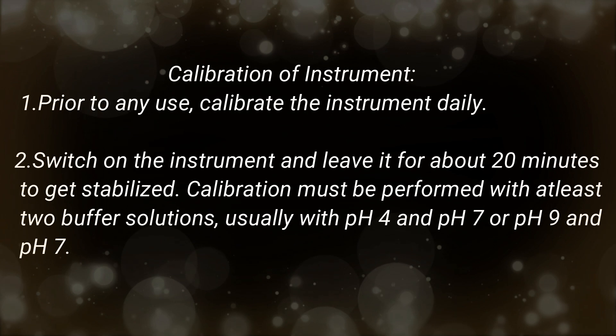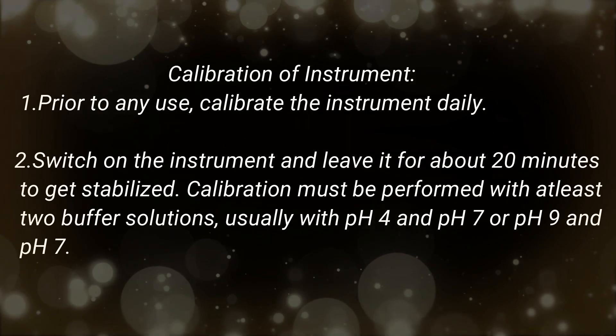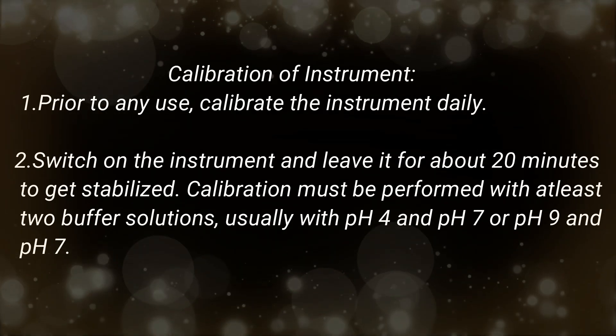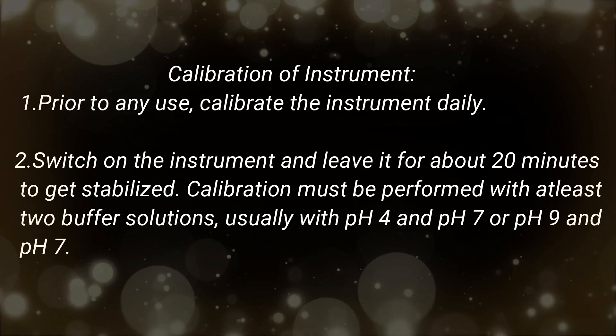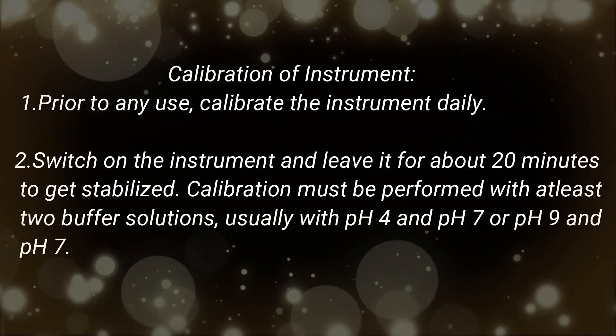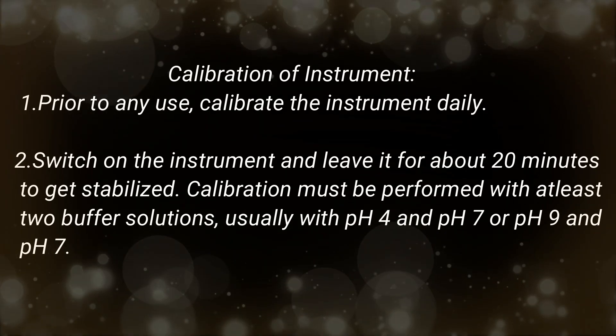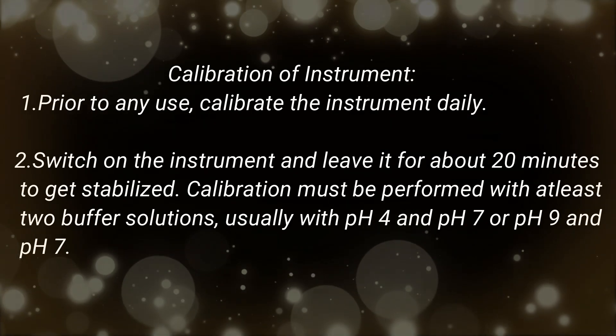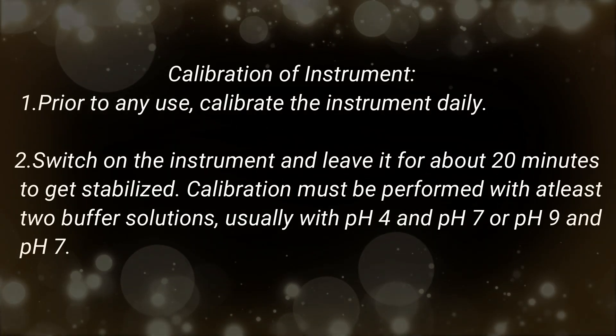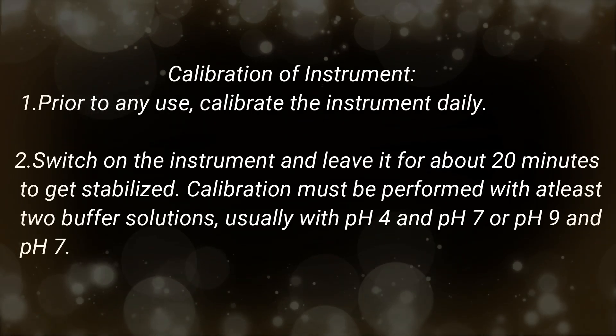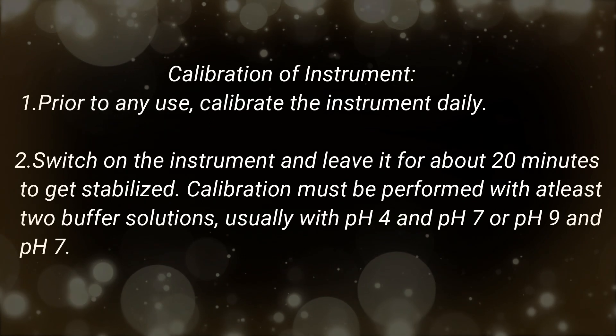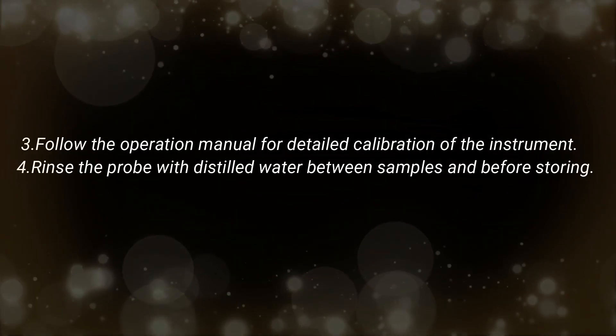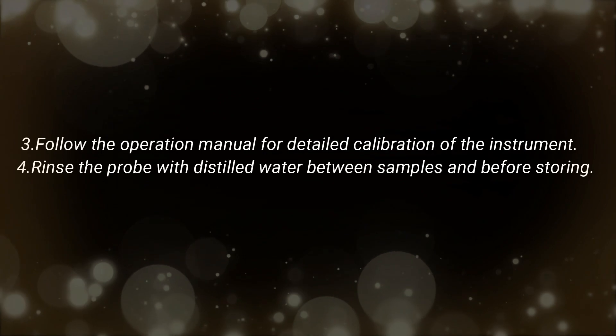Always calibrate the instrument before use. Switch on the instrument and leave it for about 20 minutes to stabilize. Calibration must be performed with at least two buffer solutions — usually pH 4 and pH 7, or pH 9 and pH 7 — following the instrument's operation manual.